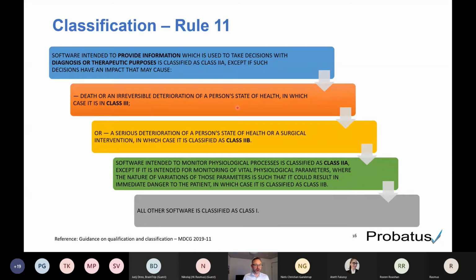If the software can cause or contribute to a state where it could cause death or irreversible deterioration, the software would be classified as class 3. If it's a serious deterioration of health or surgical intervention can relieve it, then it would be class 2B. And software that is intended to monitor physiological processes is class 2A. The last one is class 1, stating that all other software is classified as class 1.